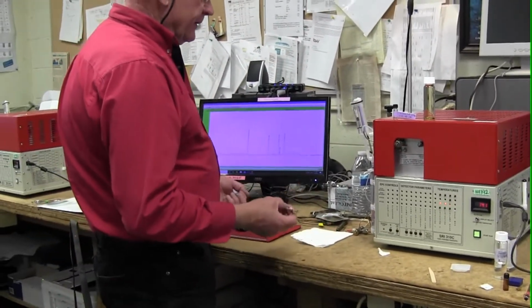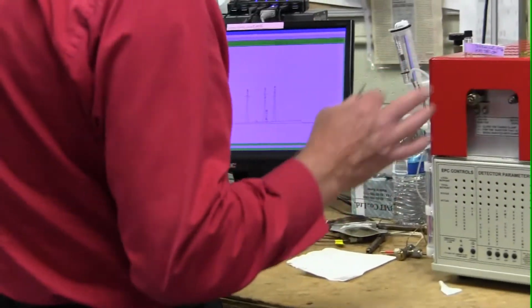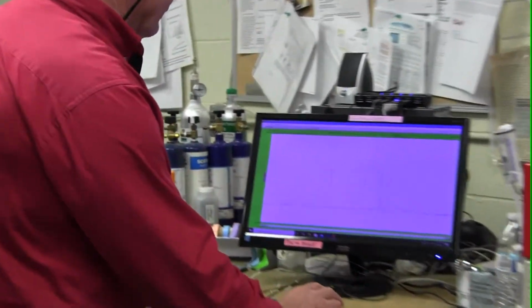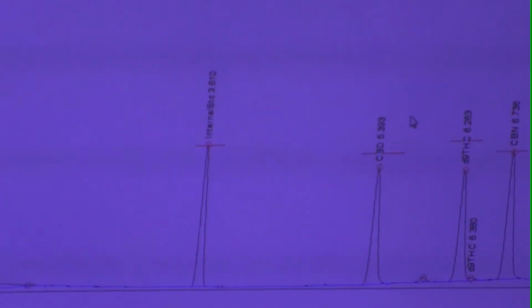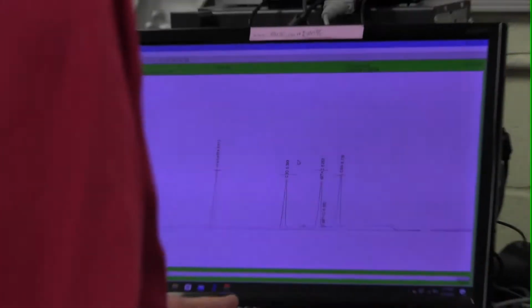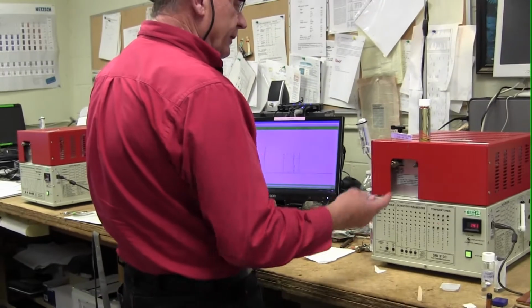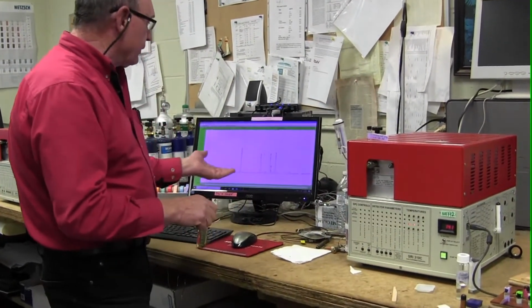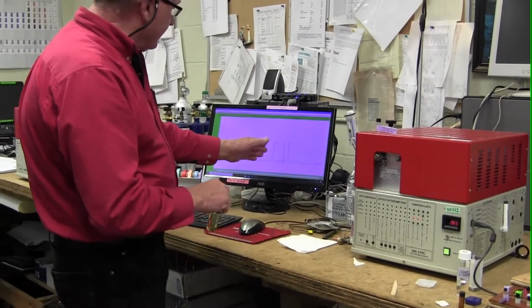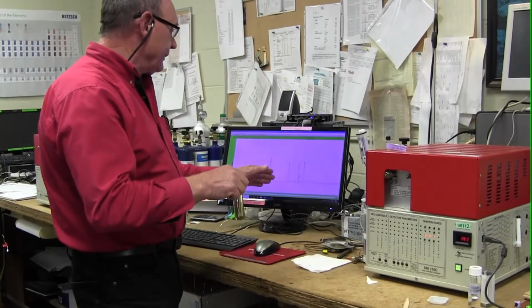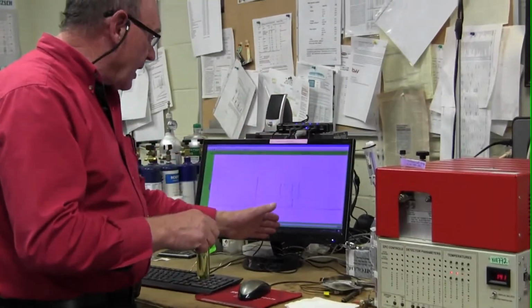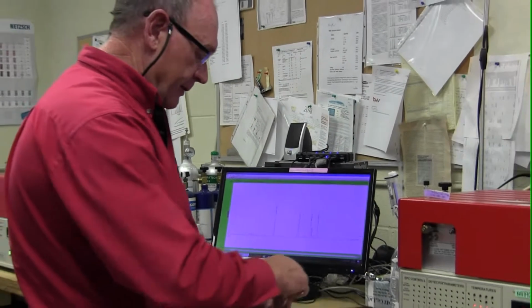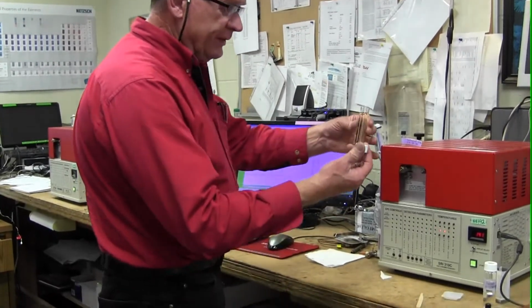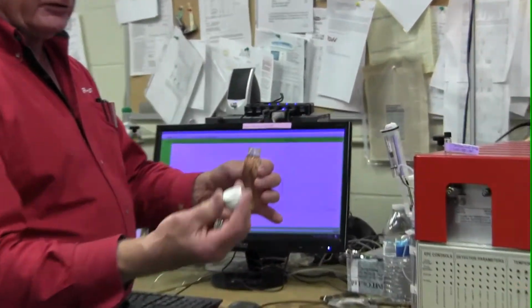So we want to inject this sample. We're looking at the water, everything looks good. Here's our calibration chromatogram. We've already calibrated. I'm going to copy this calibration chromatogram to another channel in the software where it just sits until we do something with it, but we can use it as an overlay so that we can see that the peaks that we're going to measure coming out of the Durban poison actually do line up in time with the calibration chromatogram.